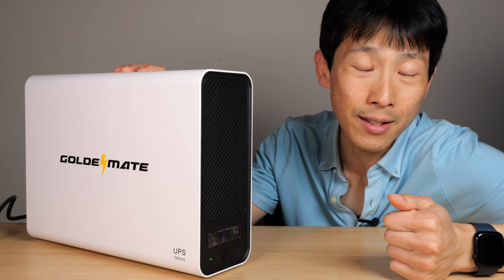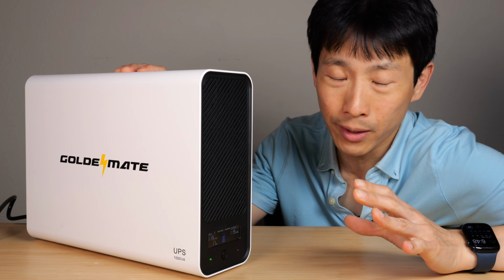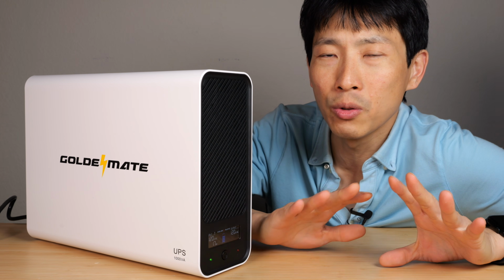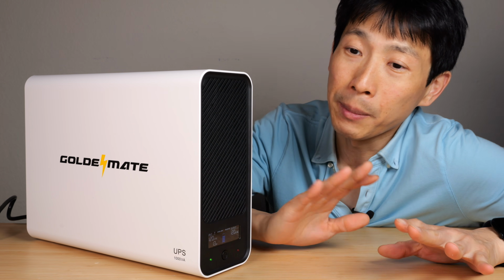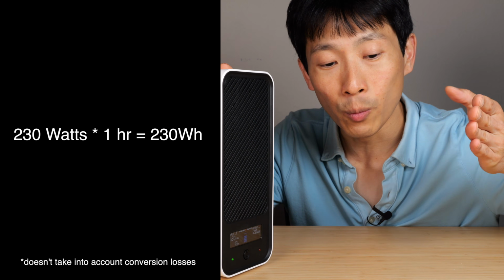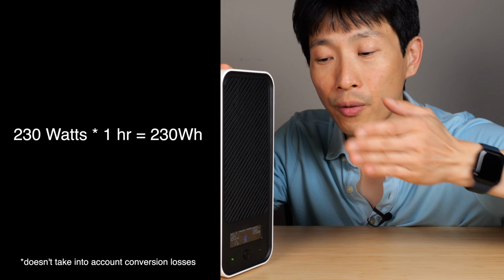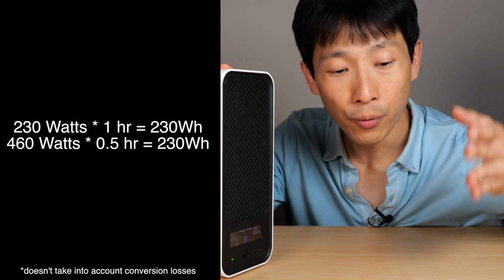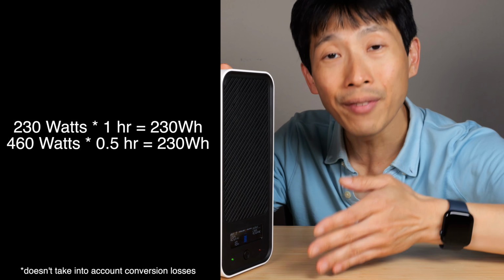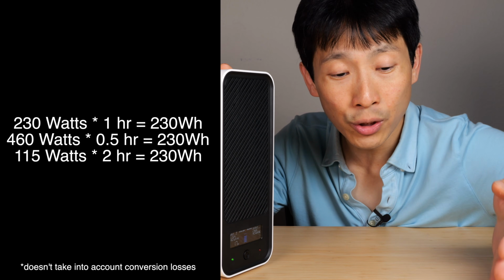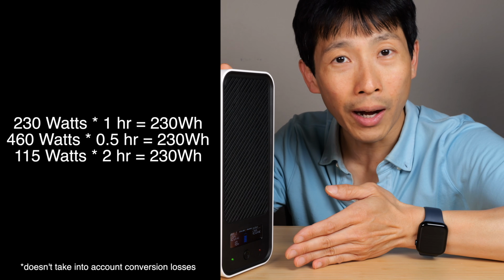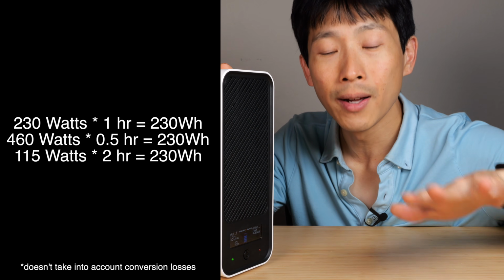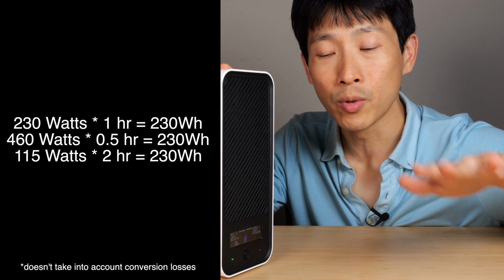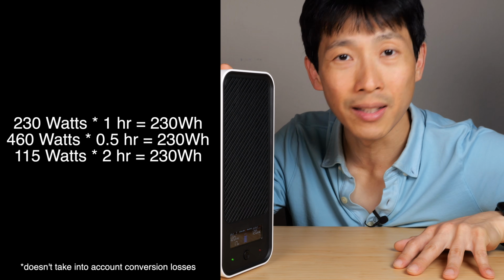This UPS has 230 watt hours. What does this mean? Your computer likely uses about 100 watts. Maybe your monitor is 50 watts. It can run 230 watts for 1 hour, or 460 watts for half an hour, or 115 watts for 2 hours. You multiply the wattage times the hour, it becomes watt hours, and you need to be less than 230.